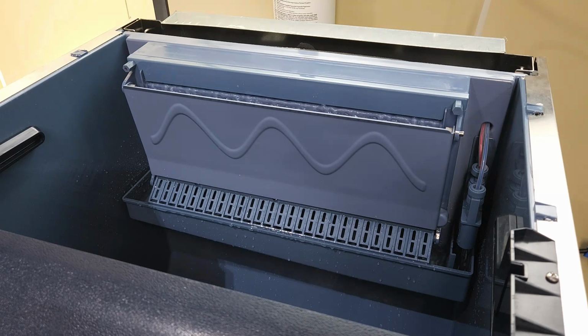You will know if it is draining long enough by listening to the ice maker. If the ice maker makes a chugging or slurping noise during the drain time before harvest, then it is draining for long enough. If it does not, then it hasn't drained enough of the water out of the trough. The ice maker drains the water out of the trough and refills with fresh, clean water every batch of ice. This is to prevent cloudy ice and to help keep the ice machine clean.